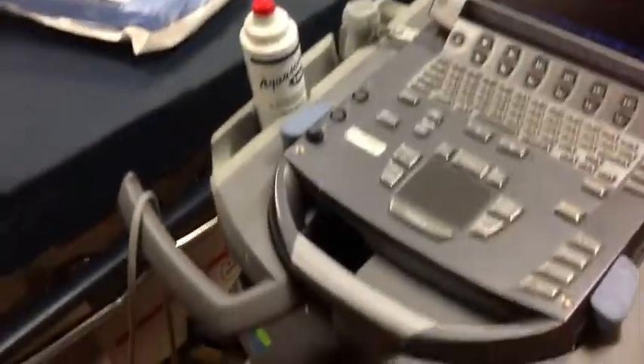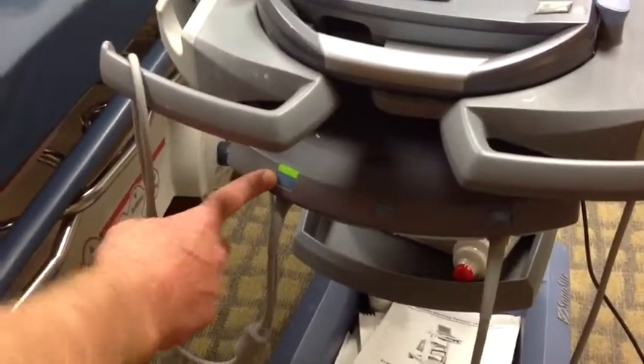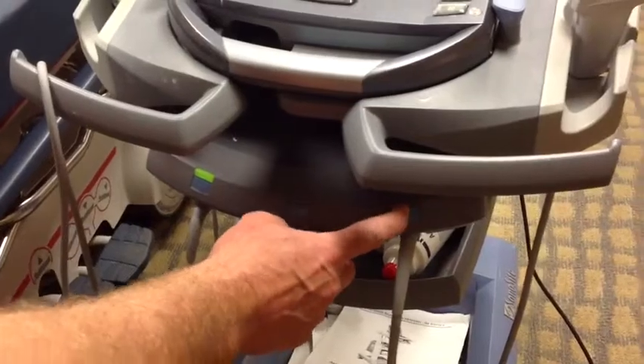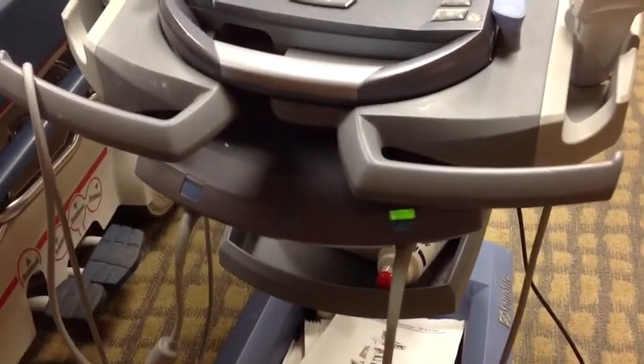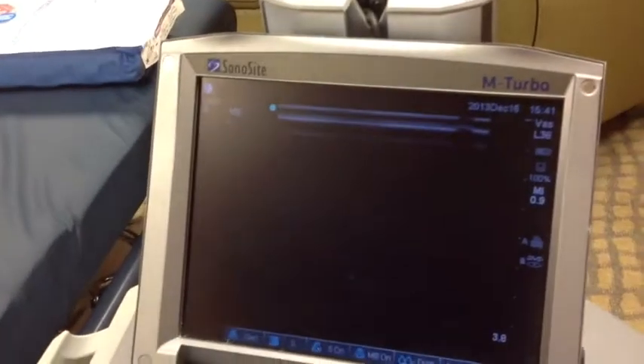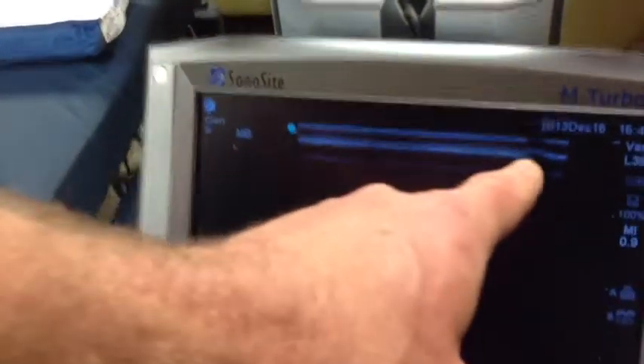Once again, the probe that we need is the high resolution probe. As you can see here, the abdominal probe light is on. We need this probe, so we're going to push this light. The light comes on, the probe boots up and activates, and you'll know it's a high resolution probe because you'll see a perfectly flat line.